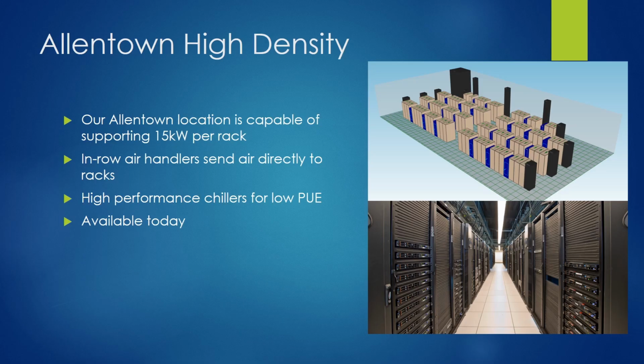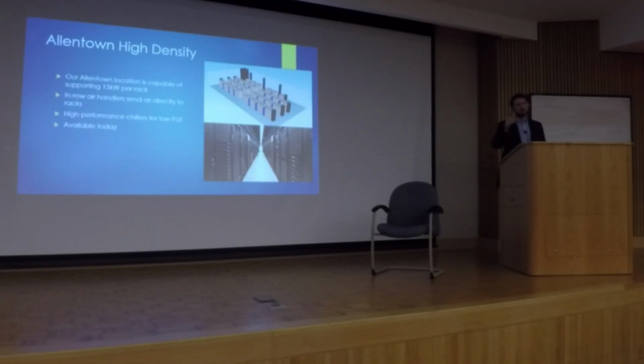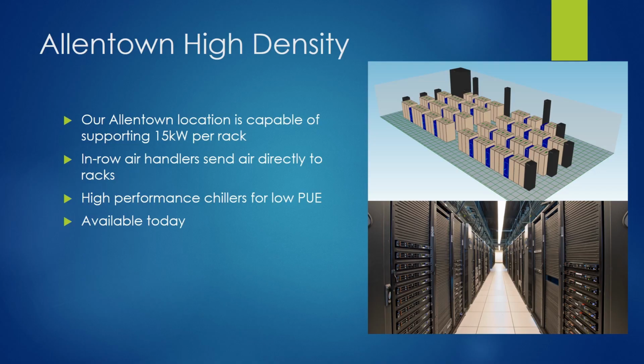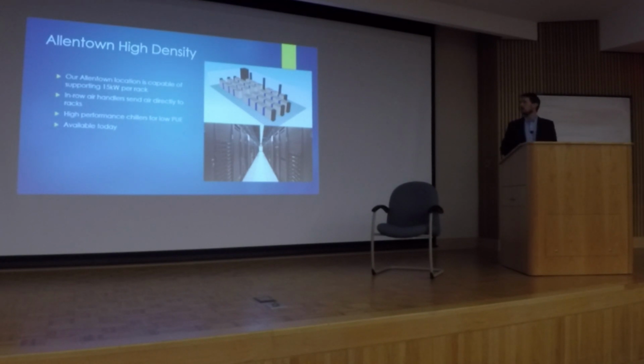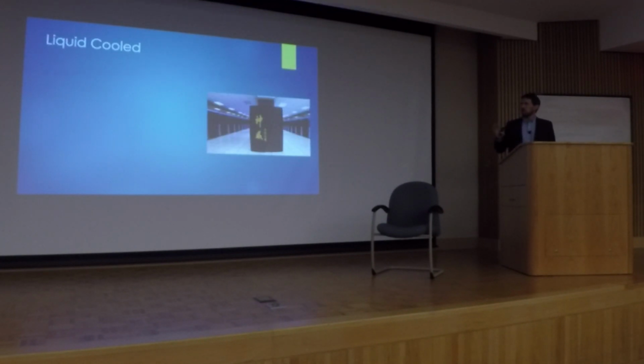So I also want to talk briefly about our Allentown facility. We can do a certain level of that high-performance computing at our Allentown facility, but because we have a different architecture where we have in-row cooling units in that space, we can really only get to about 15 kW per rack. But that's still really in that HPC range. You can do a lot of applications with that type of a setup. We use high-performance chillers, and we can achieve a very low PUE, and those are actually available today, whereas the vaults have to be customized for a given application. So, talked about air-cooled.